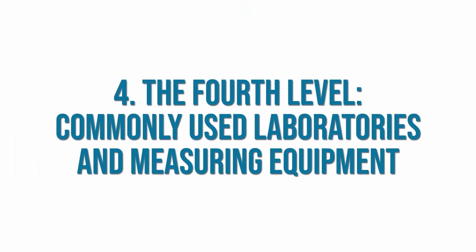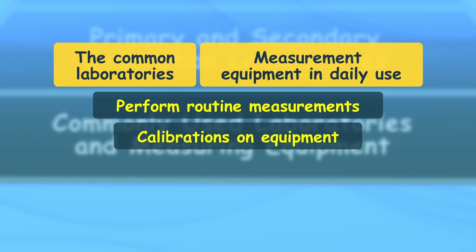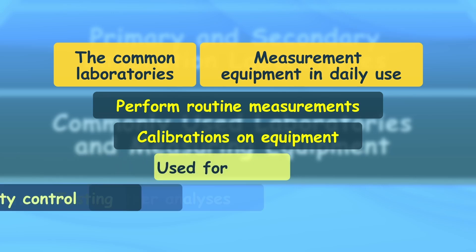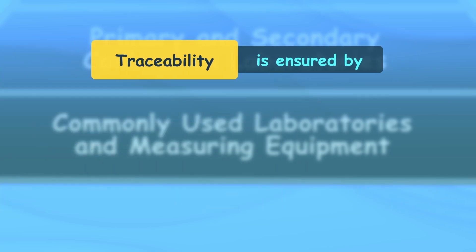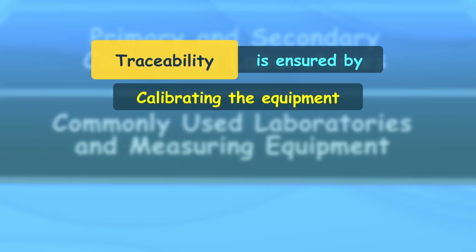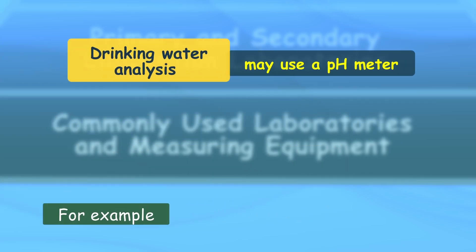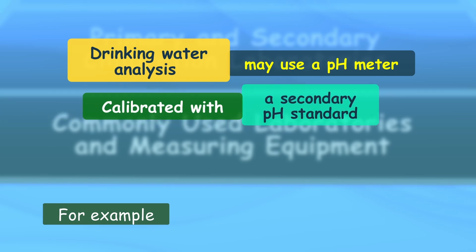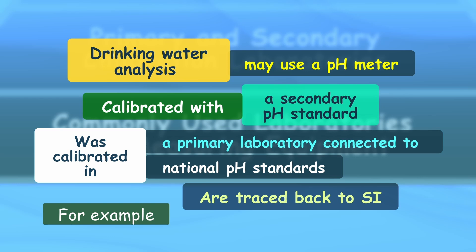At the base of the pyramid are the common laboratories and measurement equipment in daily use. These laboratories perform routine measurements and calibrations for quality control, testing, and other analyses. Traceability at this level is ensured by calibrating equipment through the traceability chain. For example, a laboratory performing drinking water analysis may use a pH meter calibrated with a secondary pH standard, which was calibrated in a primary laboratory connected to national pH standards, all traced back to the SI.